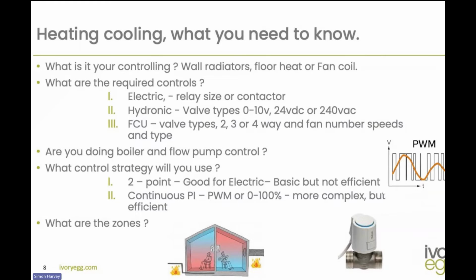The next thing we have to consider is, what is our control strategy? Our control strategy is usually dictated to us via the type of valves that we're using and the control thing, but you still have to allocate the right outputs for it. There's two major ways that we can control heating and cooling in our building, and that is 2-point. So 2-point is on or off. It's good for electrical or electric kind of loads. It's very basic, but it's not efficient.